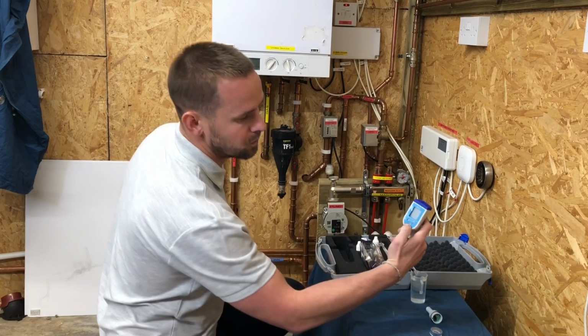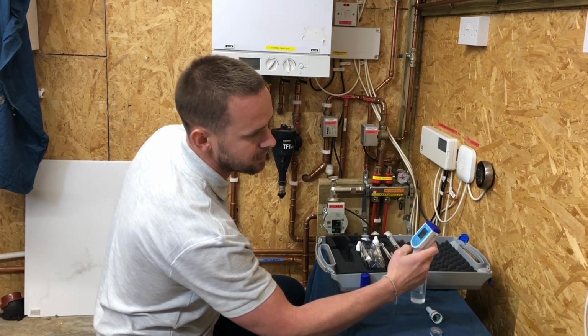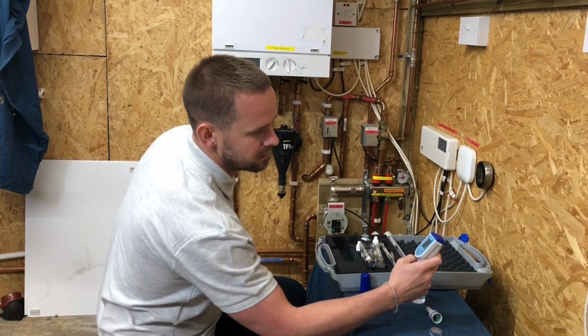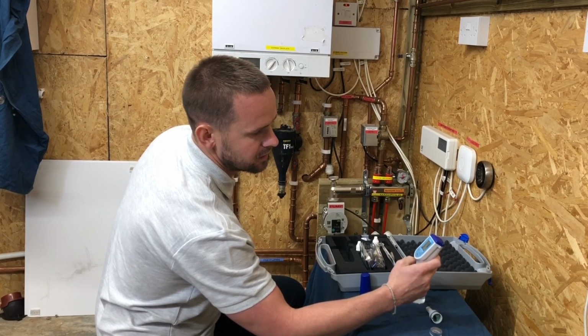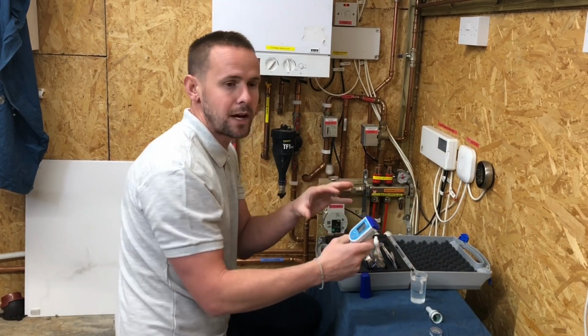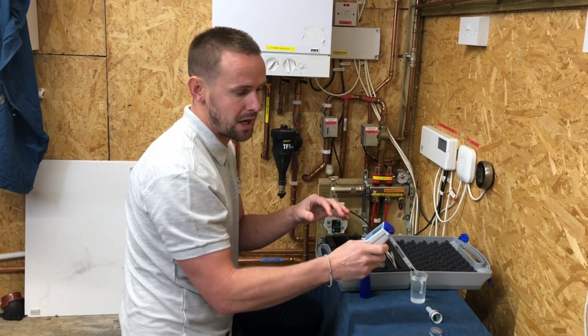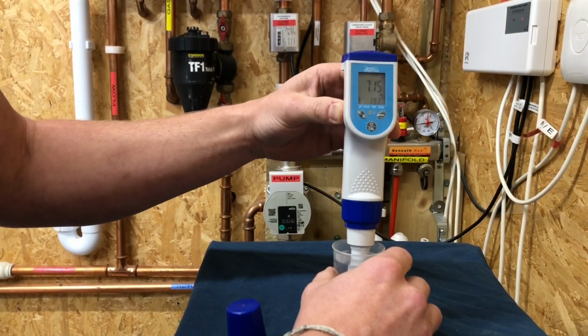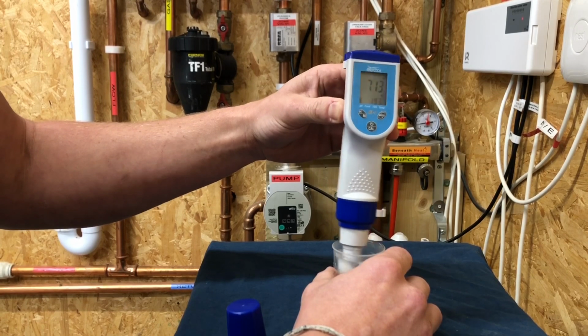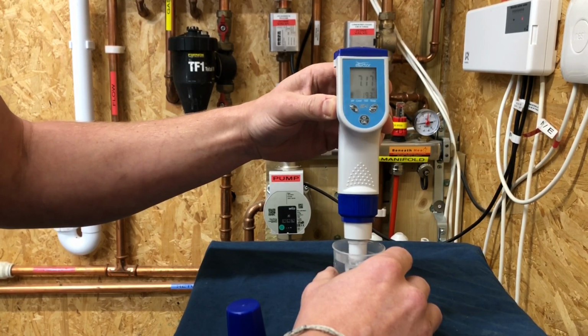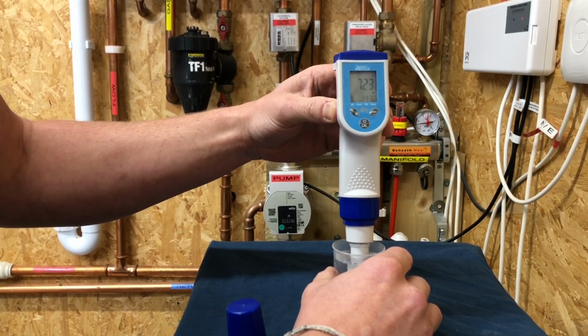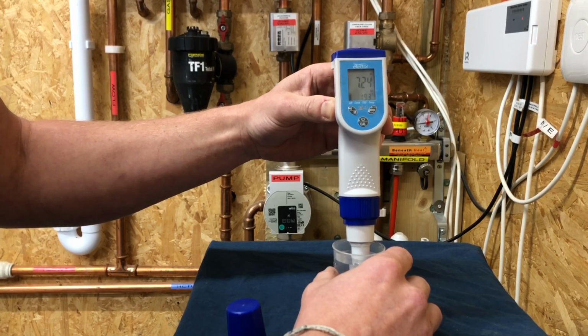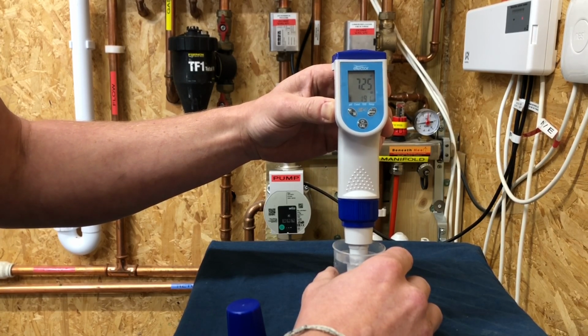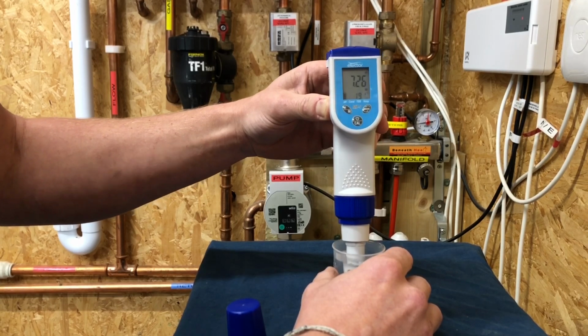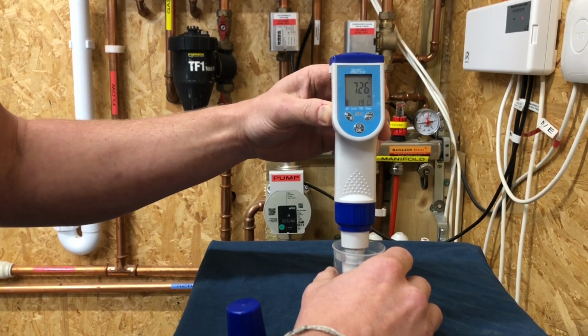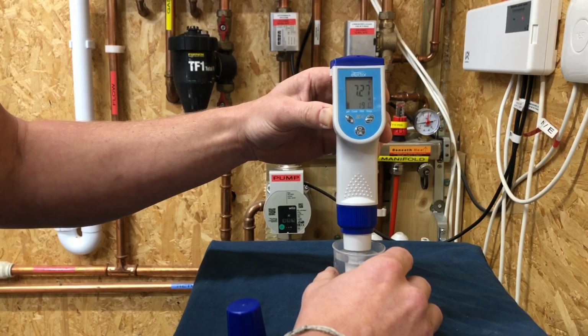So again, we'll just turn the device on. And the device itself will automatically recognise it's changed to pH. So we put the pen in, we're just going to give it a little stir. So we've got pH here of about 7.2, 7.24. VDI, realistically for this type of system that Alan's got, we want it near a 9, 8.5 and above.